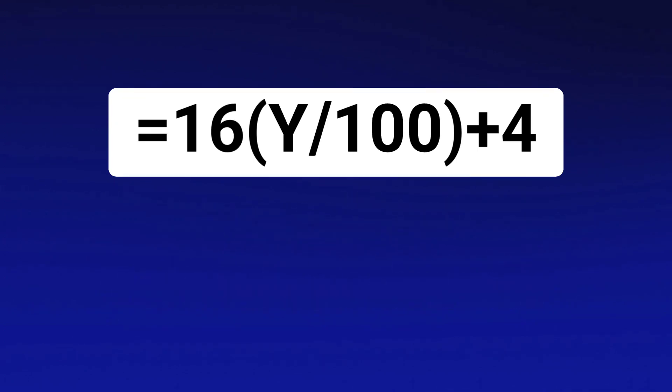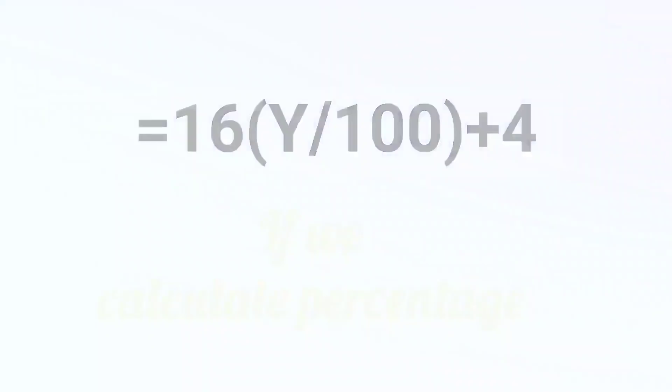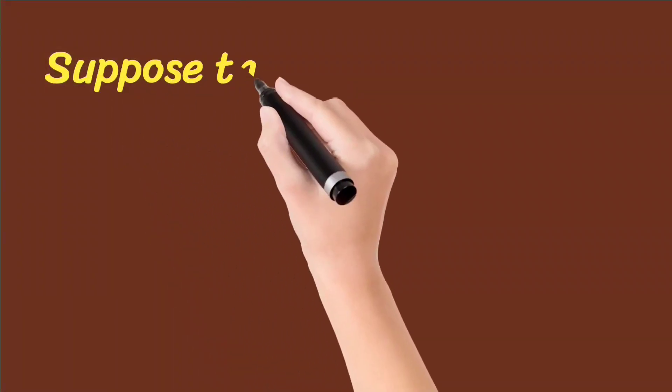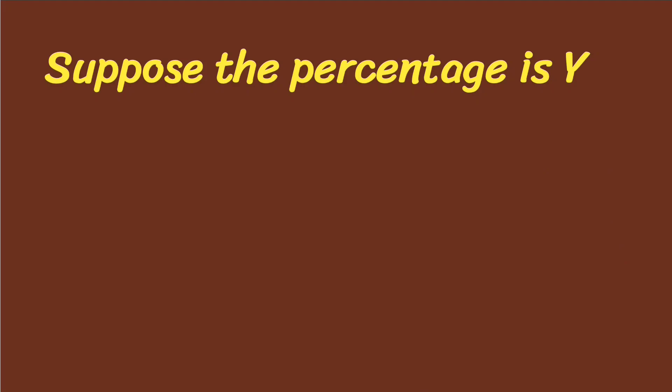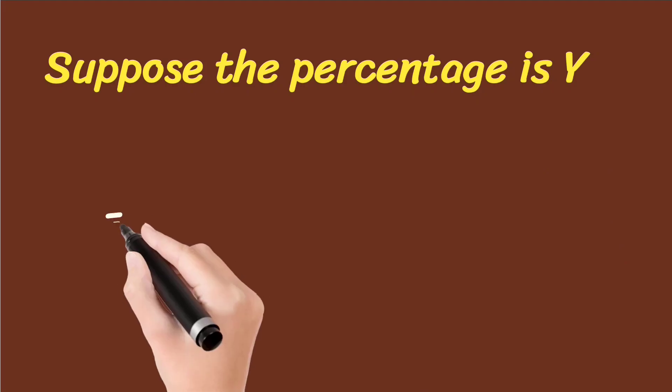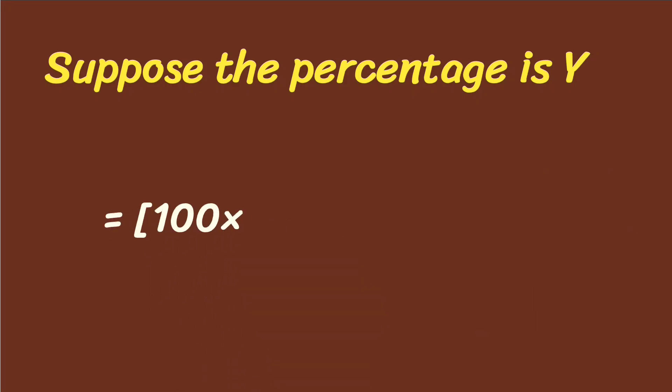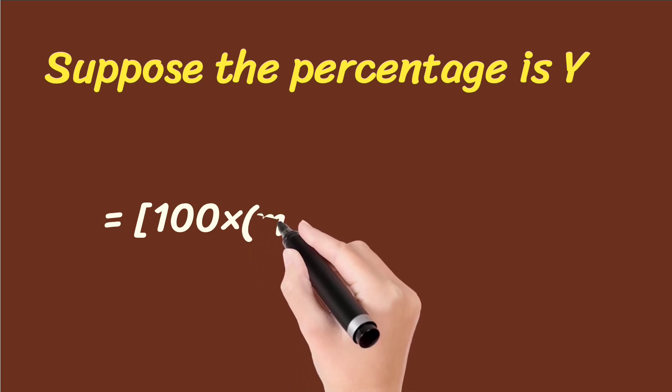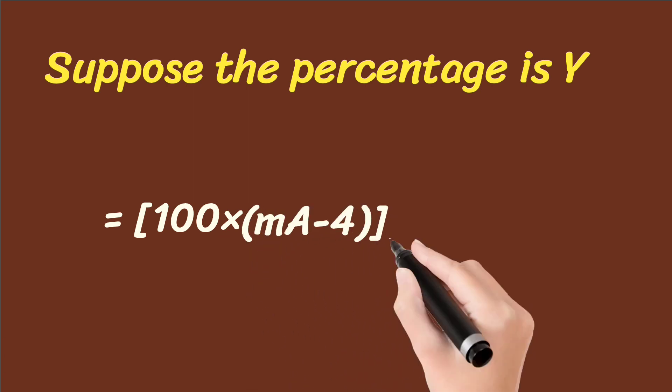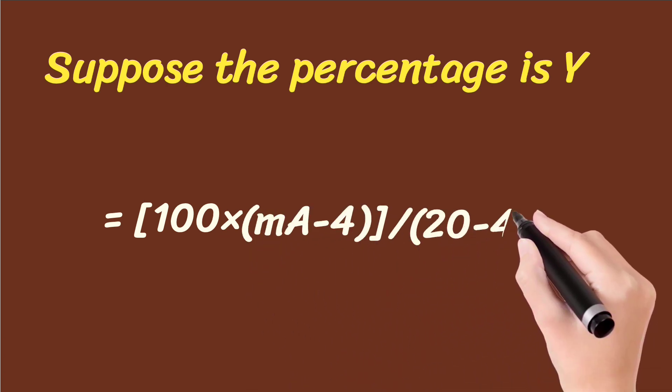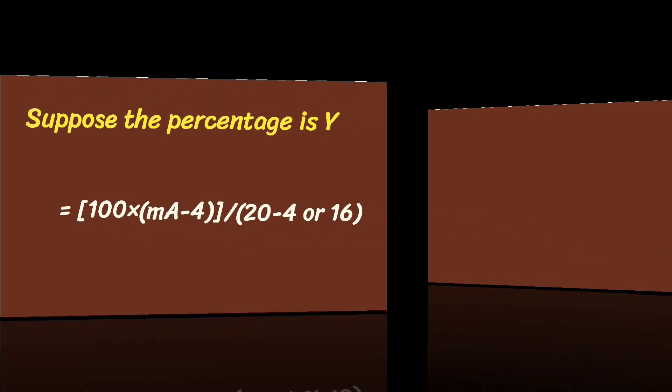And if we calculate percentage, suppose the percentage is Y, and it equals 100 multiplied by milliamperes minus 4, and divided by 20 minus 4, that means 16.